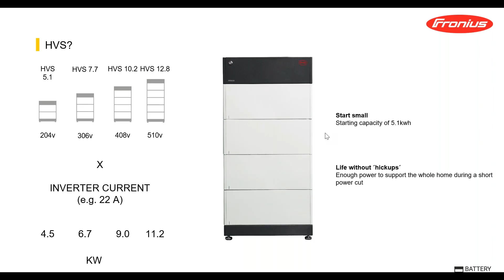So this is great for small installations where, in case of a power cut, you still want to be able to power a whole house or all the loads for a brief amount of time. So you provide more power than energy in this case. And another one of the benefits is that it allows you to start quite small. You can start as small as 5 kilowatt hours with one of these systems, and then if later on you need more capacity, you can add a bit more. But in general, this is for small residential applications.